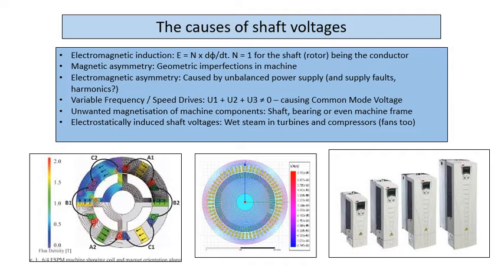Then you can also have what I call electromagnetic asymmetry, and it's related to your power supply. So if you have an unbalanced power supply, your U1 plus U2 plus U3 does not equal 0. So you'll have both a common mode voltage on the shaft, and you will also have flux linking the shaft. So you have a number of problems, and of course supply faults. Often if you have a line-to-line fault on a machine and it fails, you'll find that the earth brush has gouged an arcing path into the shaft.